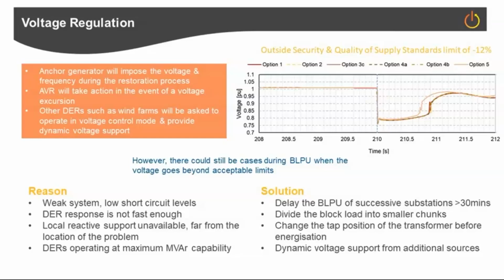What we found is that energizing transformers is quite onerous. Potentially you could have voltage drops up to 20% at the generator terminals when you are energizing transformers. A way of mitigating that could be to employ a soft start approach for restoration, starting with a reduced voltage level to reduce the impact of inrush currents and the impact of magnetizing the transformer. That is an option we're looking to pursue, to minimize the impact on voltage drops. Another thing we thought about is point-on-wave switching. If you've got circuit breakers with point-on-wave switching, that might help alleviate some of the voltage depression problems here. On the circuit side, we're testing around circuit energization.